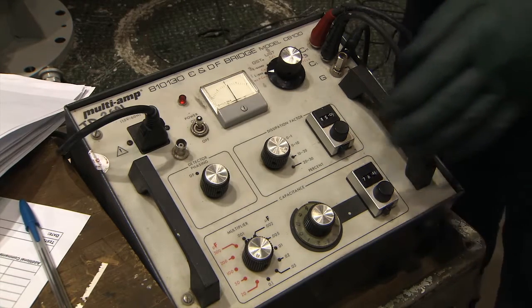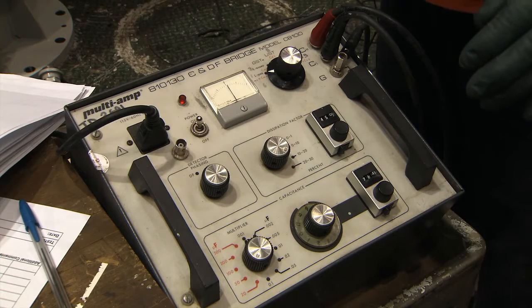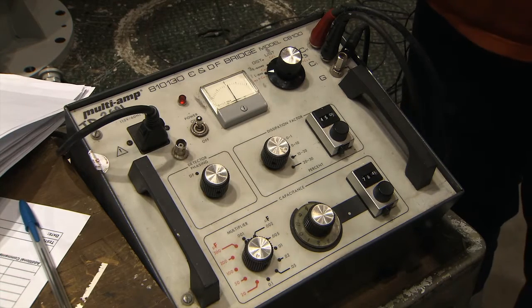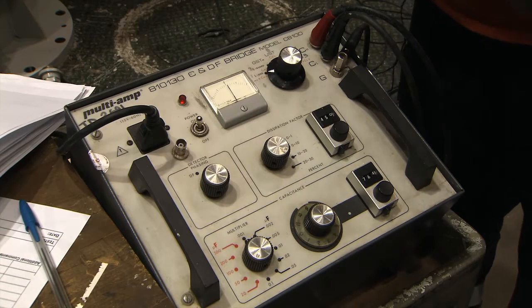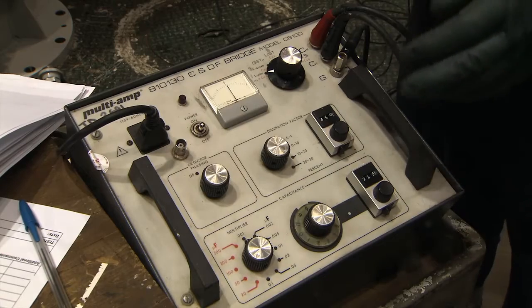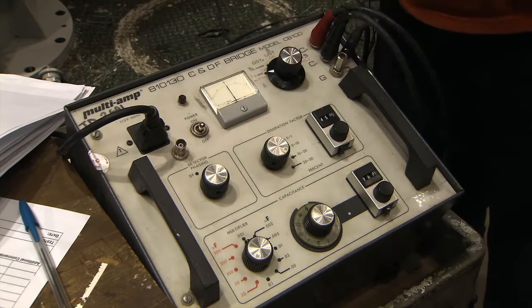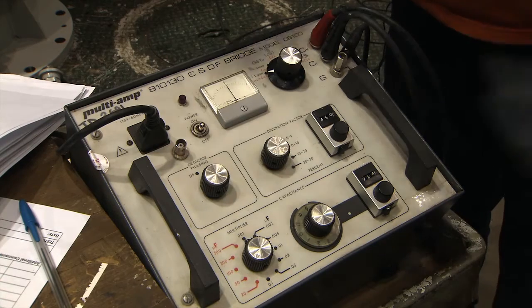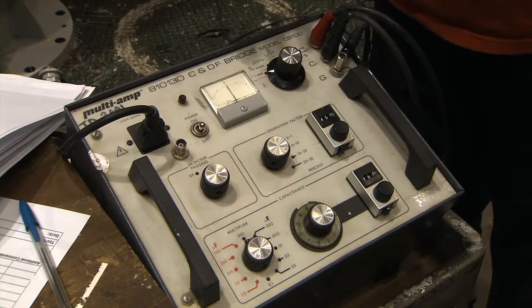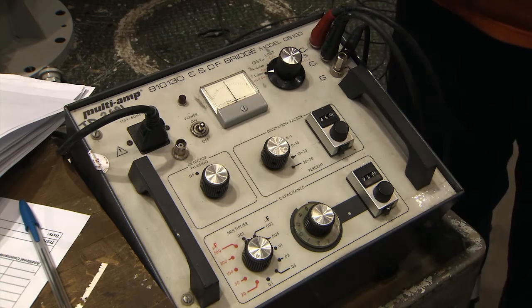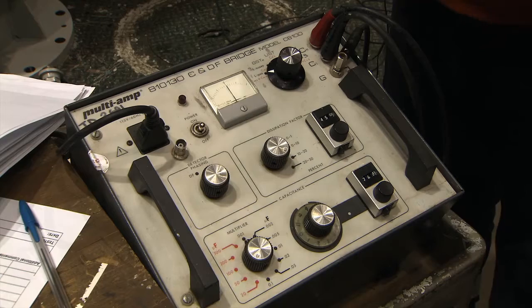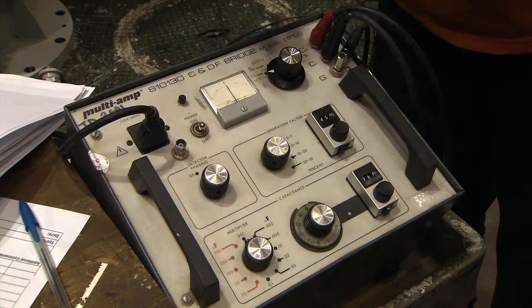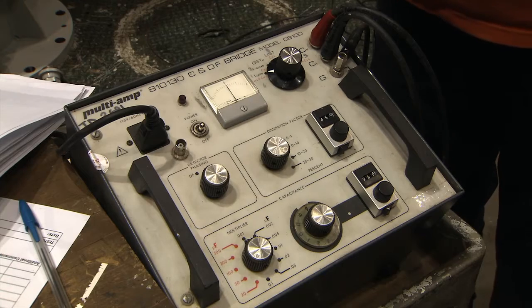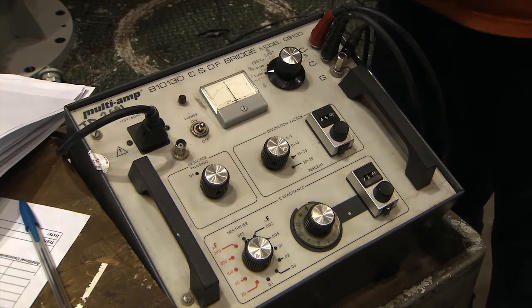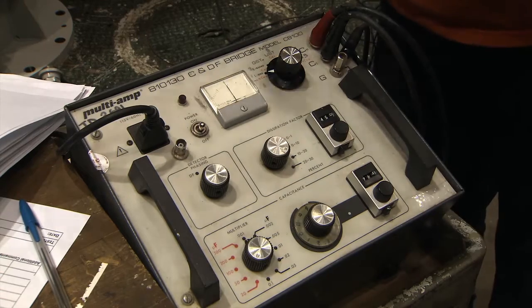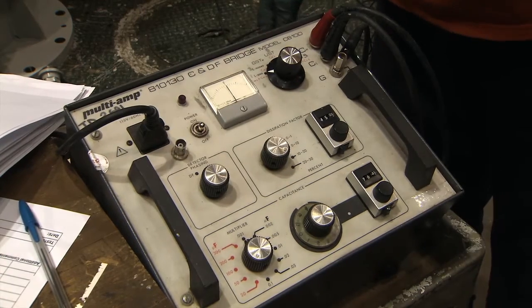We've actually sent bushings, this one particular bushing here, like the Hebron 500, we sent it to ESSA, which is in Barrie, one of the main transformer yards. Yeah, ESSA Township. We sent it there, and they installed the bushing. We had excellent readings on it. They installed it there, and all of a sudden they were having issues with the bushing, and they were asking, what did you guys do? So they made us do all these other tests on another 500 that came in here, and what it turned out to be was the transformers in the yard around them that were all active were inducing a current into their lines. Really? Yeah, that's induction. Amazing.